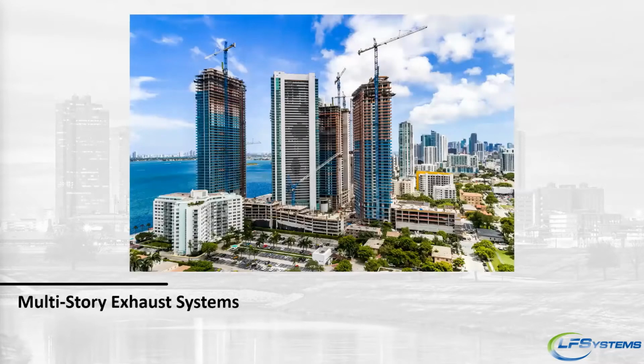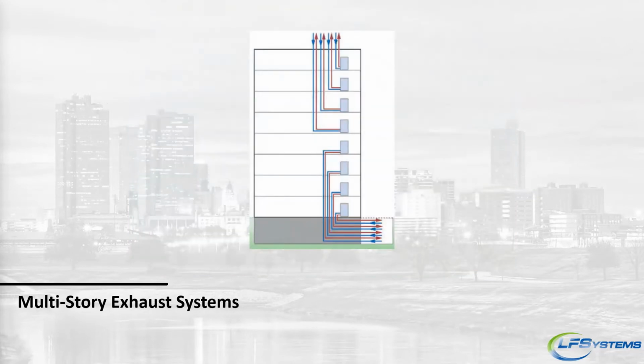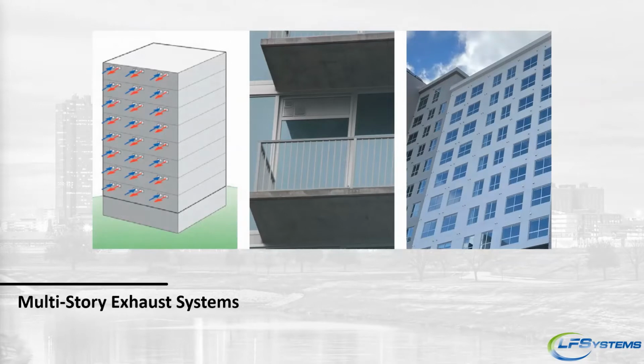So as we get into multi-story exhaust, there's a few ways of doing this when you're doing dryers and hoods and bathrooms. One way that we're not going to discuss because it looks really silly, but it is in someone's installation manual, is to have individual dryer runs going either up through the building or down through the building to an exit point. We're going to avoid that one, mostly because it's hard to get to that 35 feet and stay within that perimeter there. So the other one we're going to look at is individual sidewall.